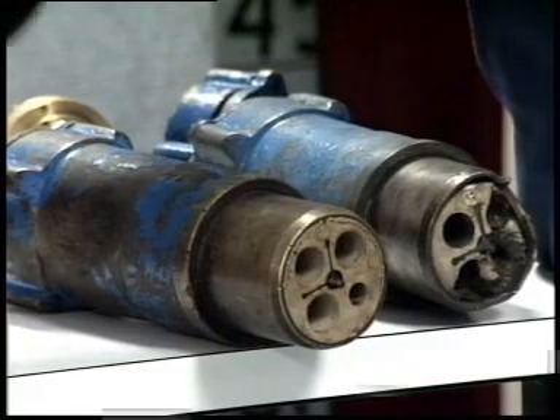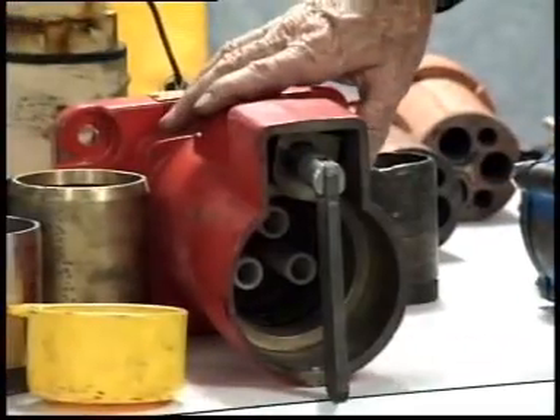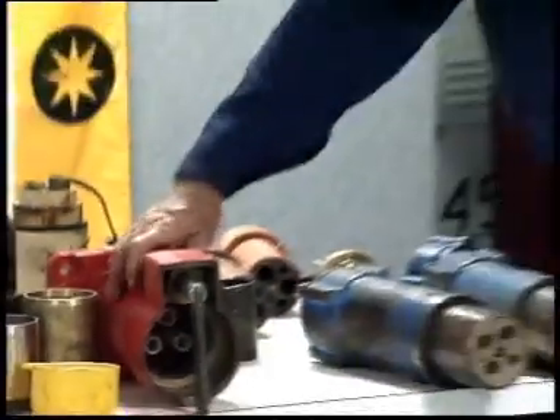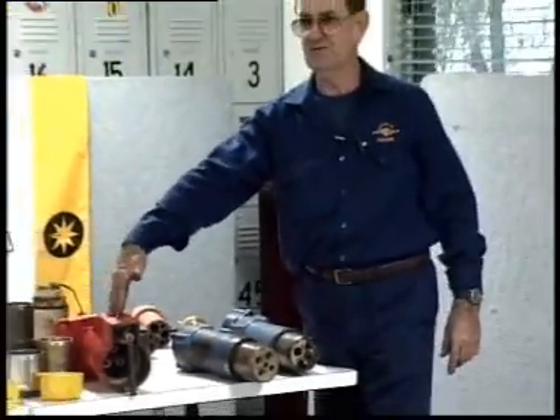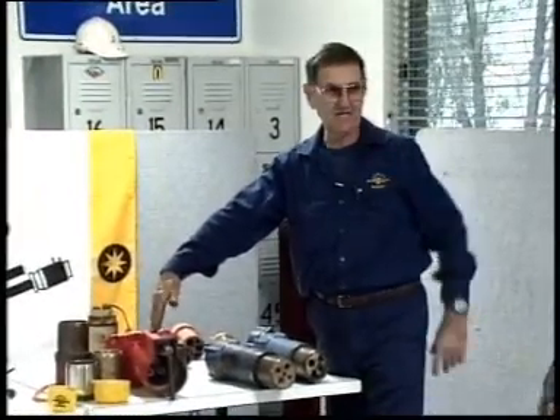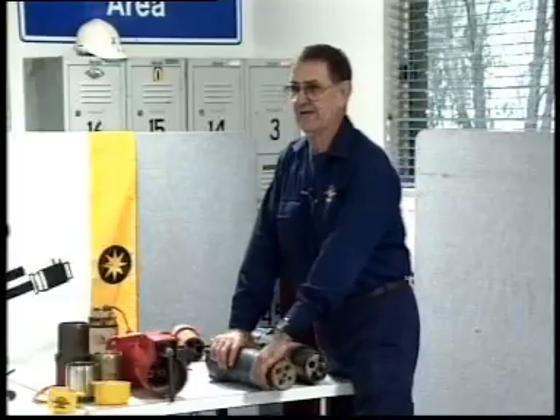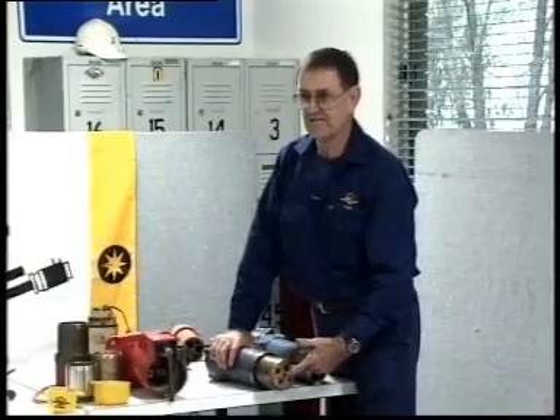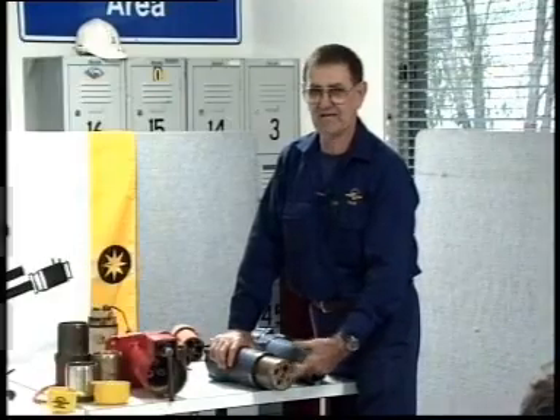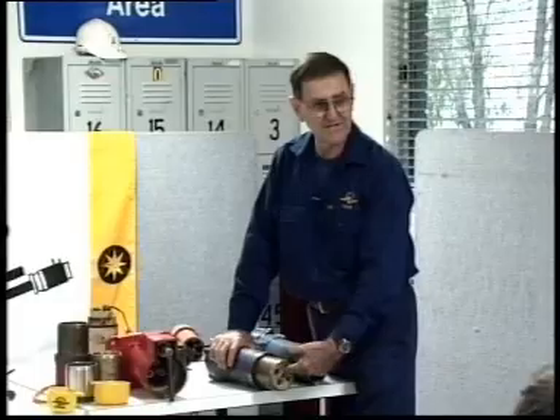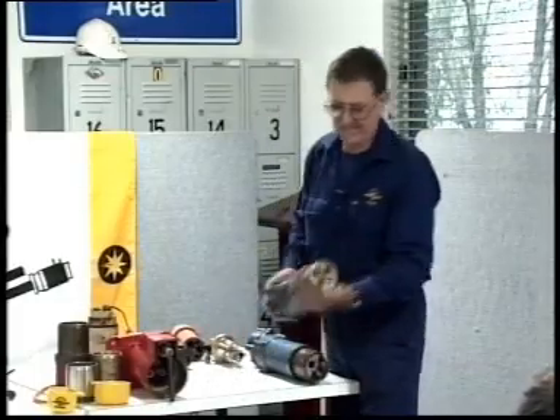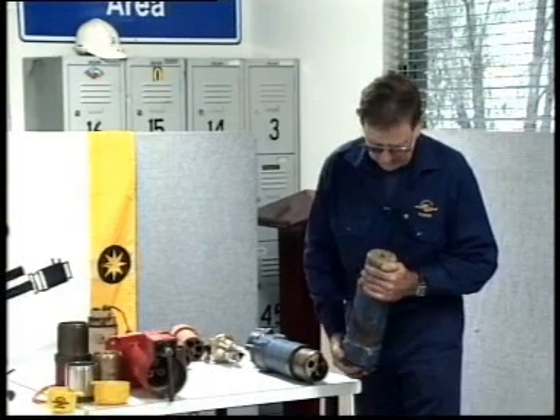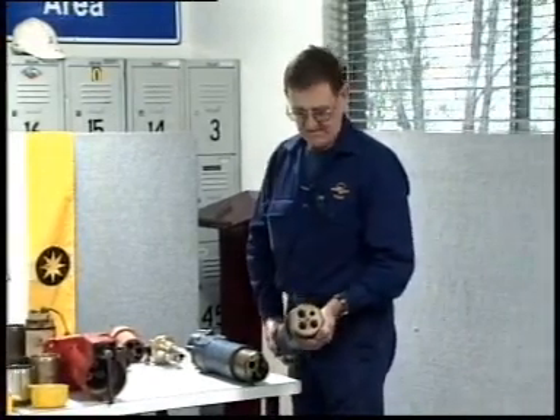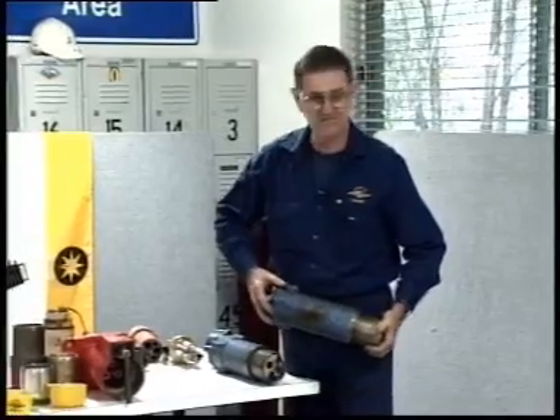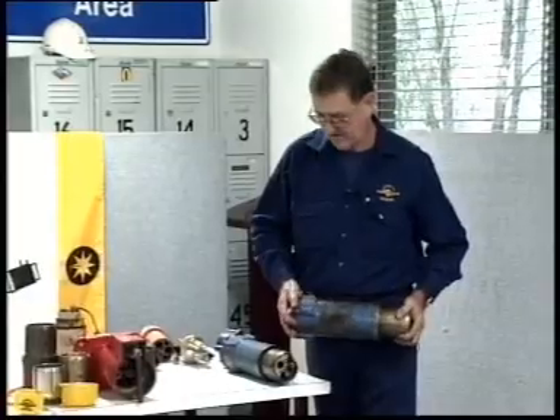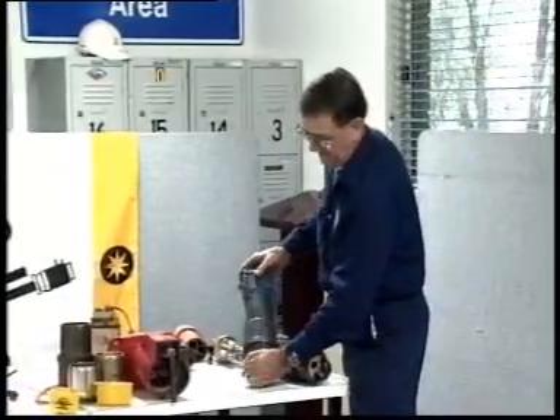We don't see this fella here, so we don't know when it goes back to the mine if the gap between that section there and the section in which you're putting it in complies. The only time these go off-site is when it goes away for what we call a Code D overhaul. So we have to measure these every time they come in. We also do a check on the pressure that's on these contacts inside with go and no-go gauges to make sure that we've got good contact on the contacts in here. Okay, so we look at the flame path on this thing. The next thing we do is look down the spout of it, make sure it looks all right and it's not full of crap. The next thing we do is just at the back end here, make sure that clamp's tight. I mean, you don't have to put a spanner on it, but it doesn't have to be loose. Just make sure it's firm. So that's the things we look at on the plug.